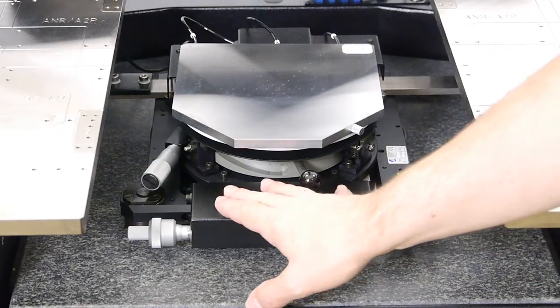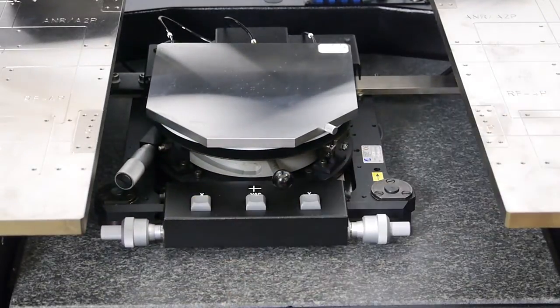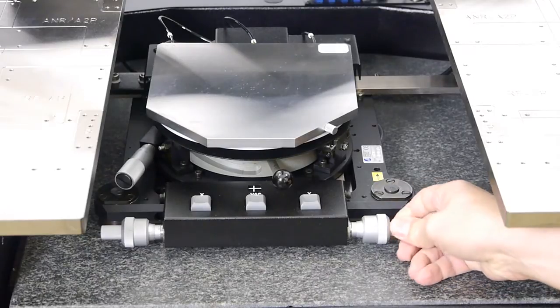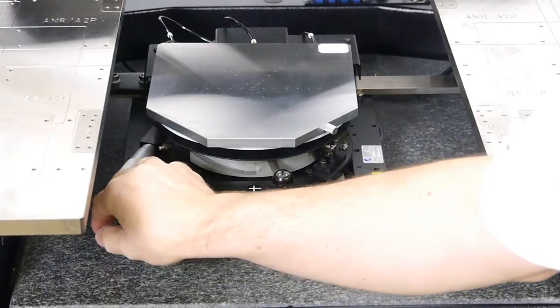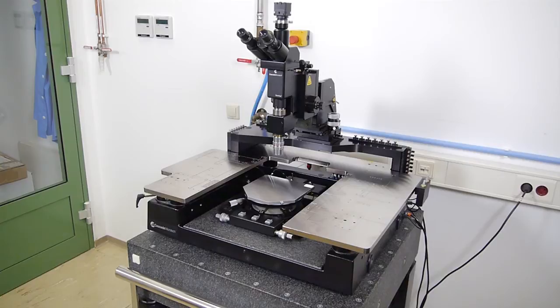We have chosen this platform as it allows a quick and fast movement between the calibration area and the main wafer area, in combination with the overlaid true submicron chuck positioning. Also, the rock-solid vibration and drift-free setup is essential for good mmWave measurements.